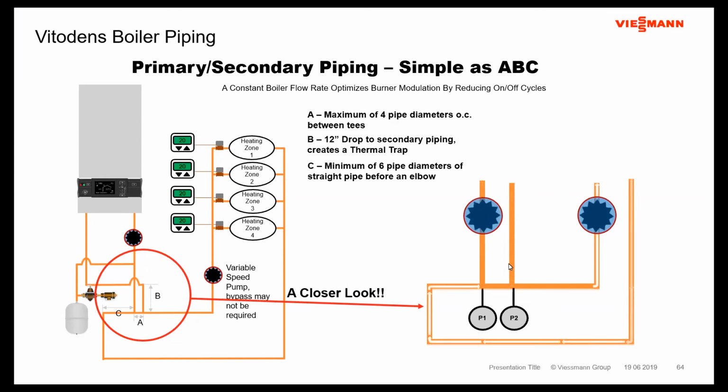So when I change the flow rate here now to this pump coming on, you'll see that the common pipe still has flow through it, but now there's no water moving up into the branches on the boiler side here. It's moving right through, right across, and right through the system here. When you see a zero pressure differential between your gauges, the fluid's not going to see a pressure differential.